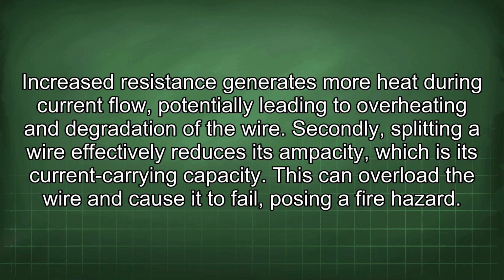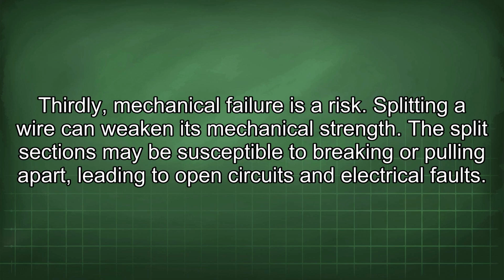Secondly, splitting a wire effectively reduces its ampacity, which is its current carrying capacity. This can overload the wire and cause it to fail, posing a fire hazard. Thirdly, mechanical failure is a risk. Splitting a wire can weaken its mechanical strength. The split sections may be susceptible to breaking or pulling apart, leading to open circuits and electrical faults.